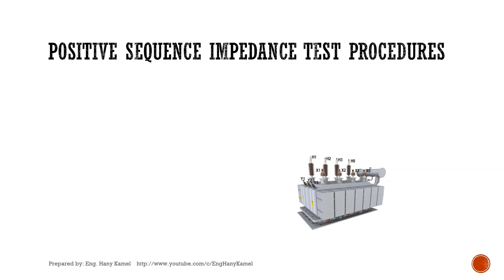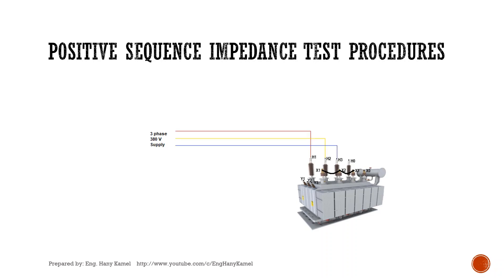This test is important to check if there is any deformation in the windings or connections. If we consider a power transformer with three voltage levels, we will check it between each two voltage level windings. We will start with impedance between the high voltage and low voltage windings. We will short circuit the low voltage winding, and the tertiary winding will be open. Three phase supply will be injected to the high voltage side.